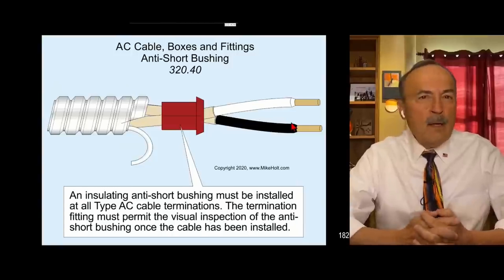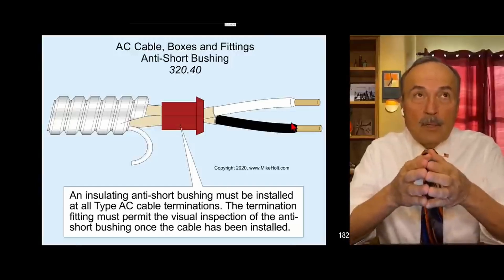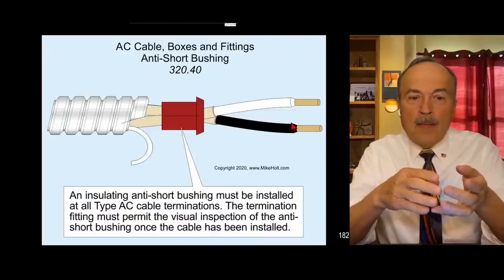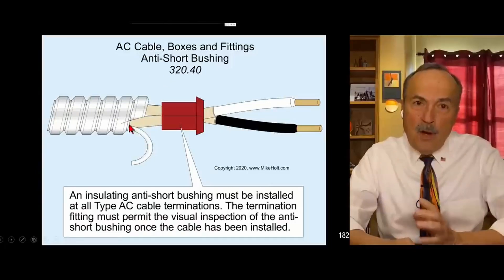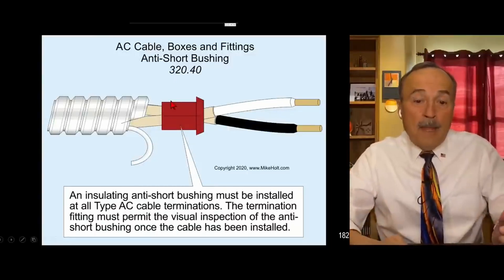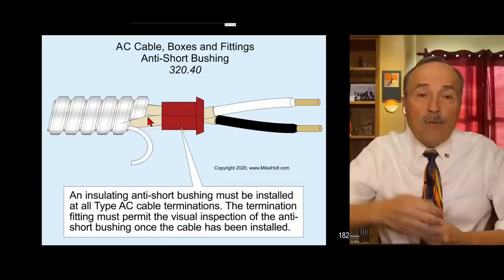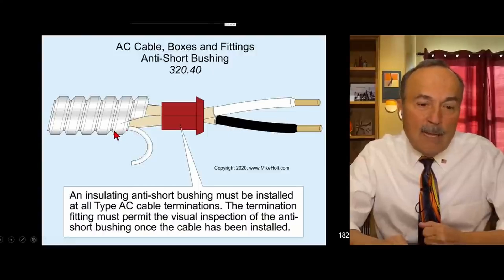Armor cable came out before MC cable - BX came out first. They had fittings that required a plastic anti-short bushing - it doesn't have to be red but I think it only comes in red. You take the 18-gauge aluminum bonding strip for armor cable and you cut it off. That 18-gauge is a bonding jumper - it bonds one steel convolution to the next, making the sheath of armor cable listed as an equipment grounding conductor. That's 250.118.